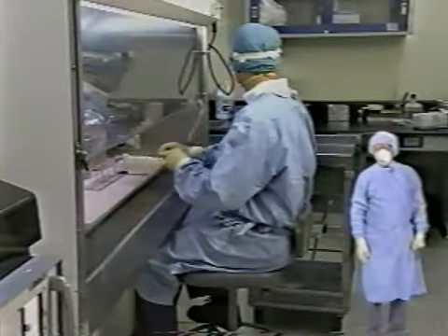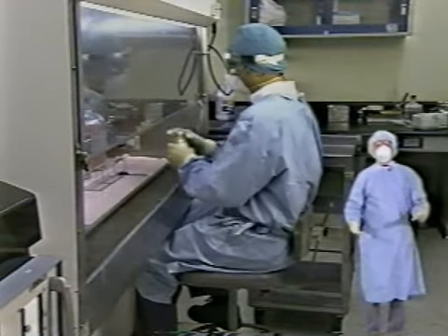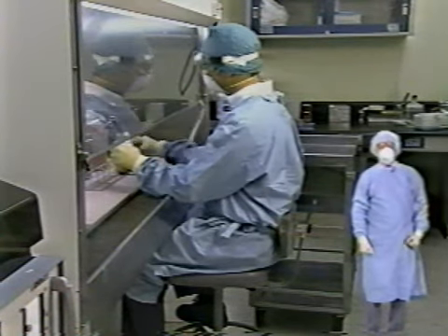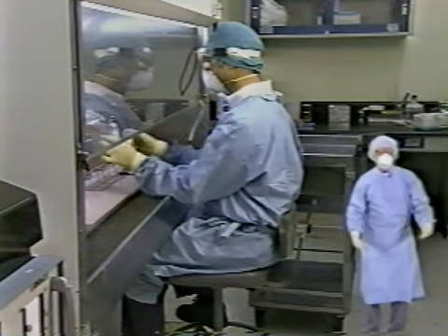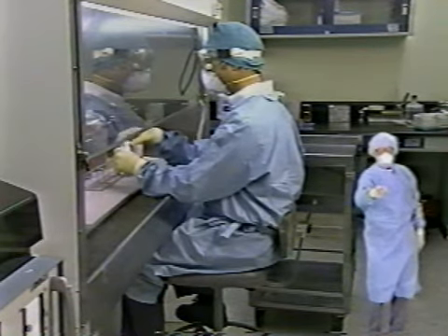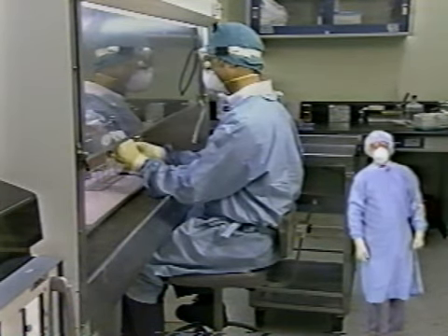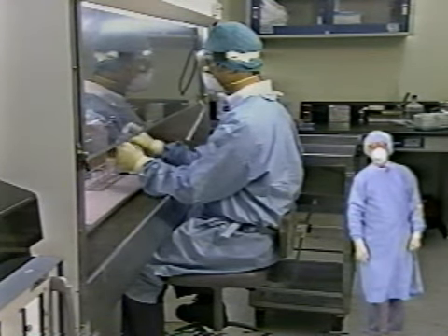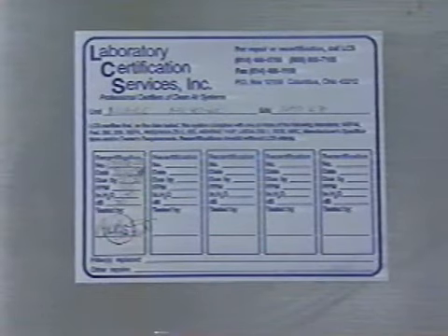Without the proper airflow in the BSC, aerosolized pathogens might escape the confines of the safety cabinet. Accidental splatters could contaminate work surfaces, even other specimens, or maybe even you. Never work in a BSC when you are uncertain about the airflow. You're right. Remember, BSCs should be certified at least annually by authorized technicians to assure the correctness of the airflow.